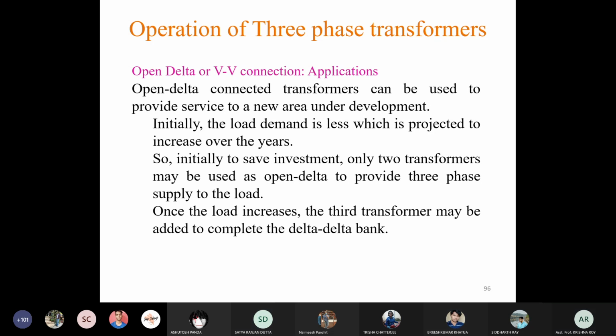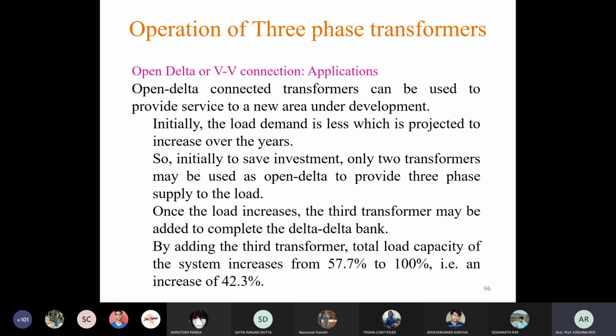Yes, sir. So when one transformer gets damaged, that is an accidental case, but this intentional open delta connection we make intentionally, to save investment. By adding the third transformer, the total load capacity of the system increases from 57.7% to 100%, that is an increase of 42.3%. That means by installing the third transformer we are increasing the capacity of the system by 42.3%. That is the most important advantage of this system.